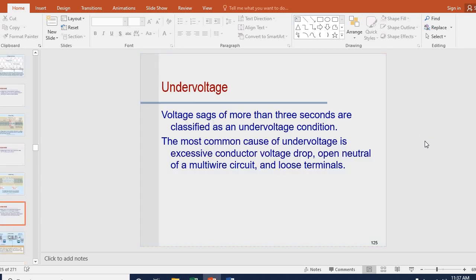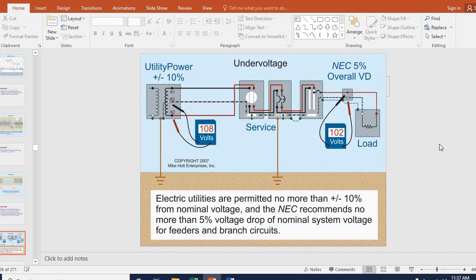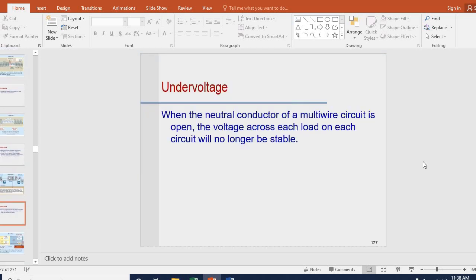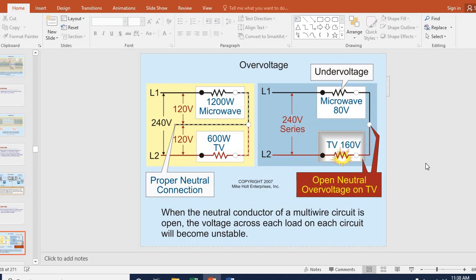Under voltage. Voltage sags of more than 3 seconds are classified as an undervoltage condition. The most common cause of undervoltage is excessive conductor voltage drop, open neutral of a multi-wire circuit, and loose terminals. Loose terminals, probably the most common source of voltage sags in the country. That's just saying the electric utilities permitted no more than 10% from nominal voltage. NEC recommends no more than 5% voltage drop. Nominal system voltage for feeders and branch circuits. Over voltage, when a neutral conductor of a multi-wire circuit is open, the voltage across each load on each circuit will become unstable. Very unstable.